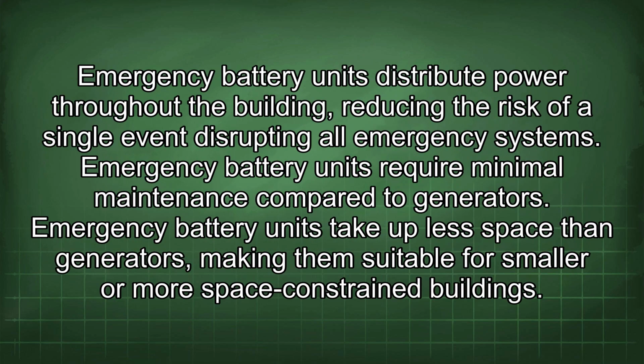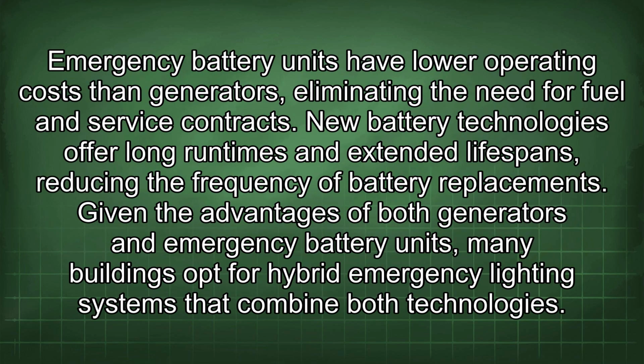Emergency battery units distribute power throughout the building, reducing the risk of a single event disrupting all emergency systems. Emergency battery units require minimal maintenance compared to generators. Emergency battery units take up less space than generators, making them suitable for smaller or more space-constrained buildings. Emergency battery units have lower operating costs than generators, eliminating the need for fuel and service contracts. New battery technologies offer long run times and extended lifespans, reducing the frequency of battery replacement.